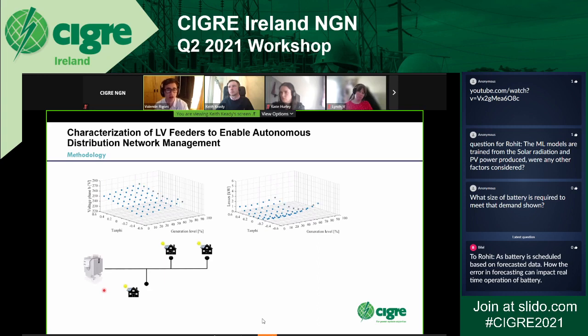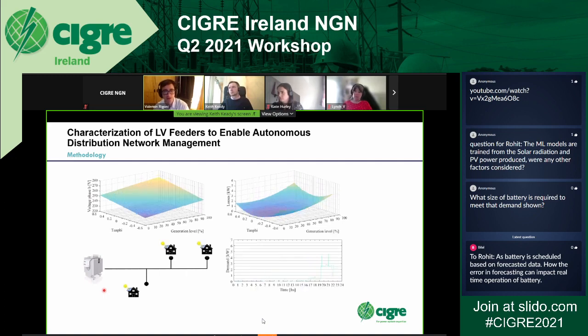So for instance, how the voltages in a phase at a certain node are going to change if we change the PV power injections, what the losses are going to be doing, what the currents are going to be doing, etc. And grabbing that information, we apply regression analysis, which is that machine learning, and we obtain a surface or a polynomial that would express how your voltage at that point is going to be affected by what the PVs are doing.